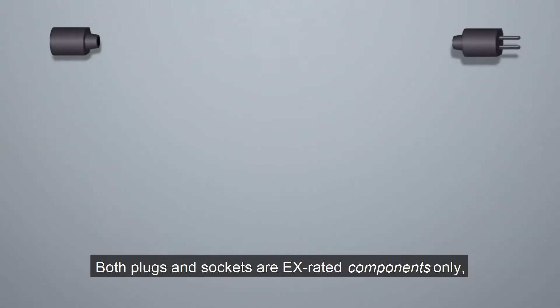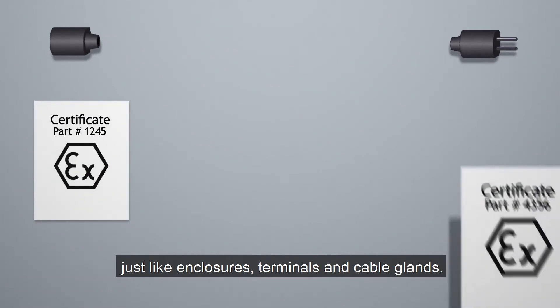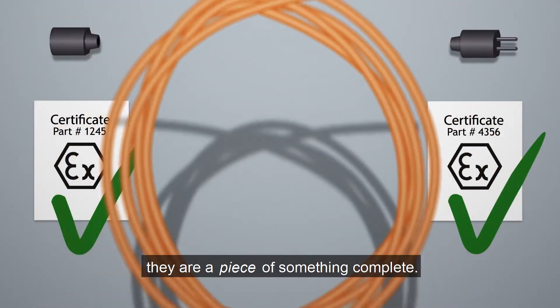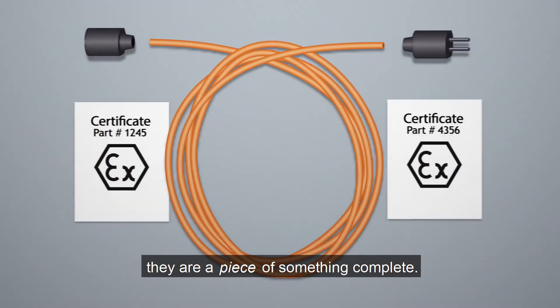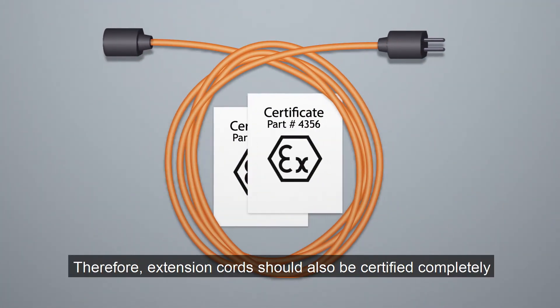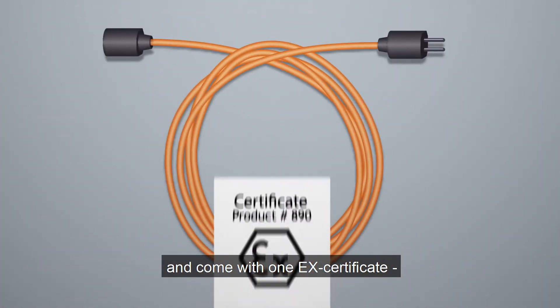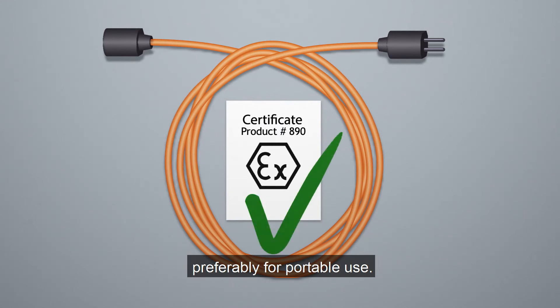Both plugs and sockets are EX-rated components only, just like enclosures, terminals and cable glands. They're a piece of something complete. Therefore, extension cords should also be certified completely and come with one EX certificate, preferably for portable use.